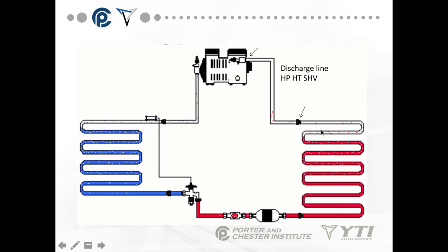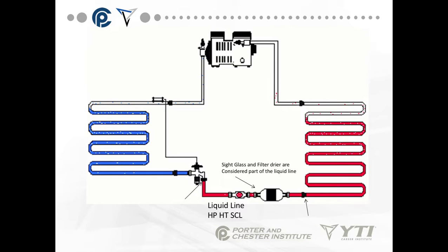Remember, the condenser first desuperheats, then condenses, then sub-cools. Once the refrigerant is now a sub-cooled liquid, it moves into the liquid line — that's why it's called a liquid line. The liquid line includes the sight glass and the filter dryer. It starts at the outlet of the condenser and goes to the metering device.